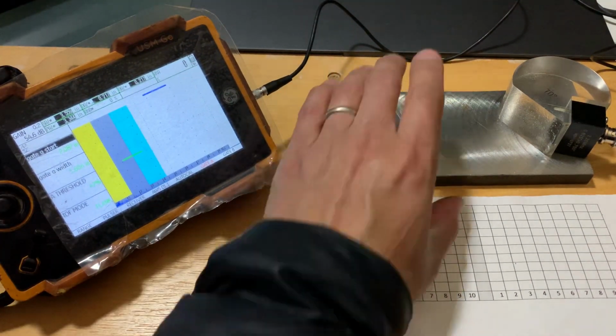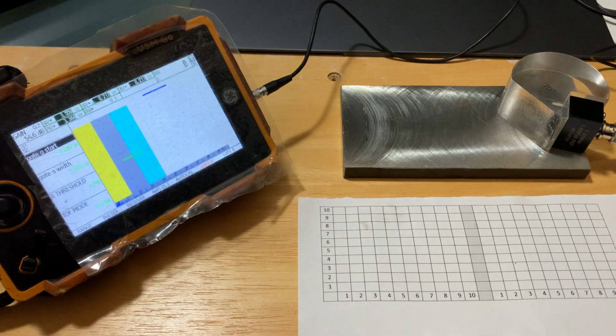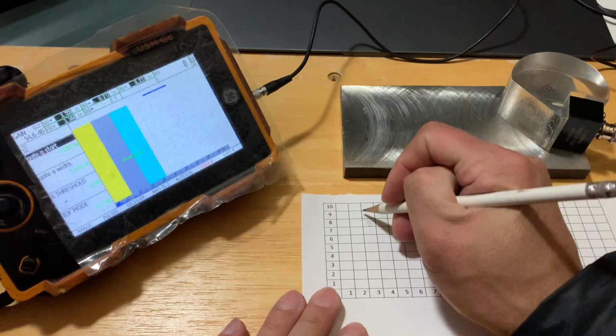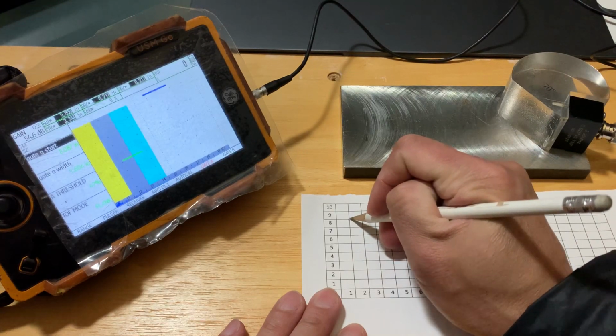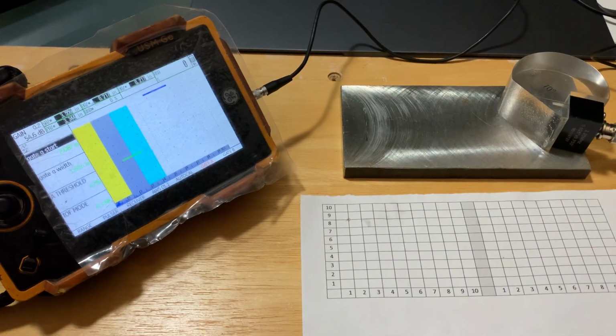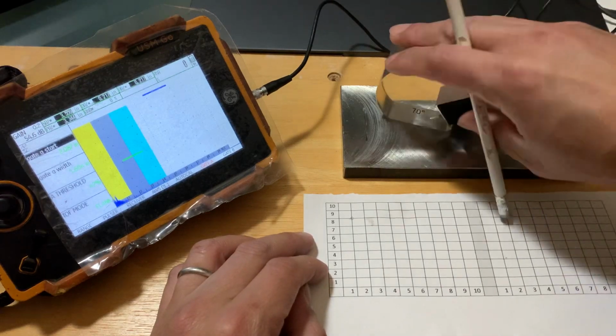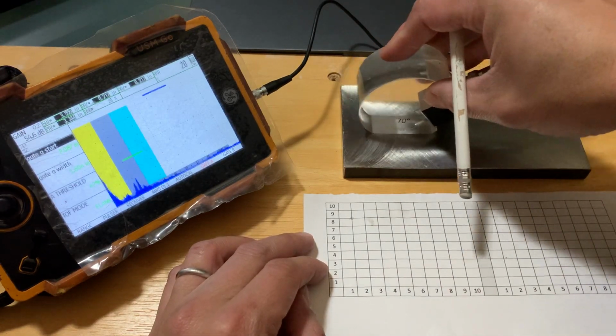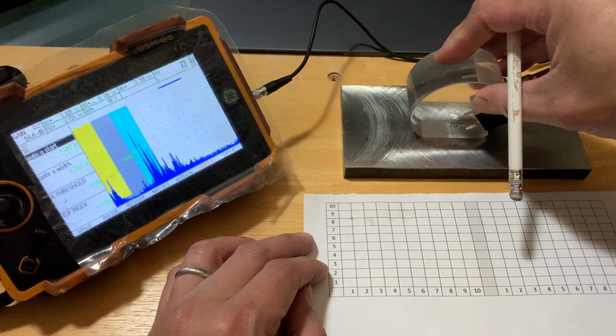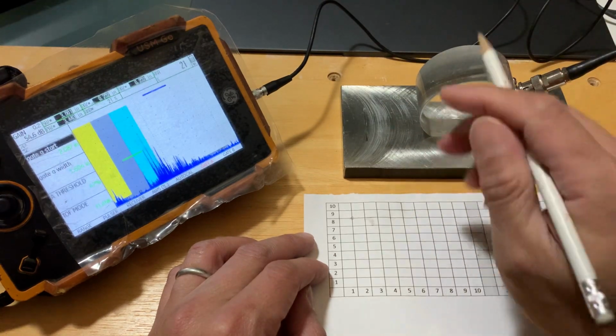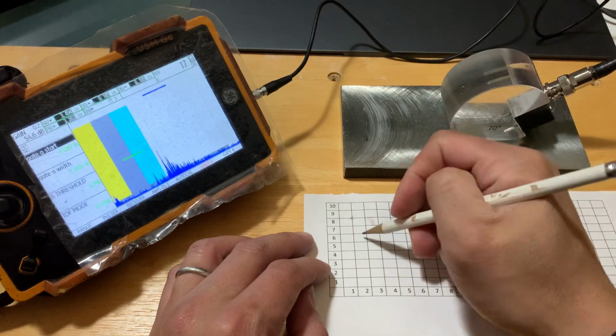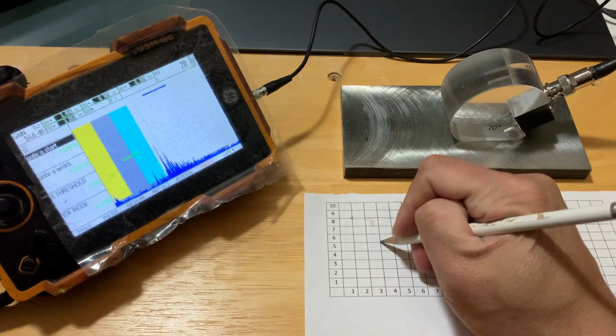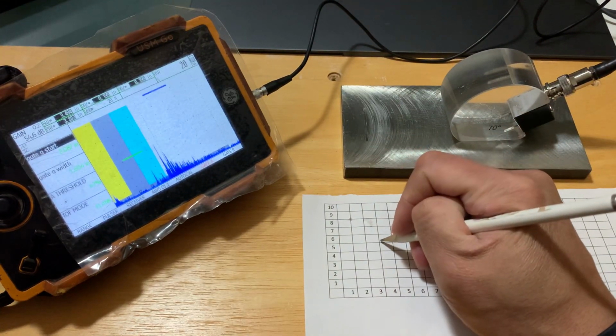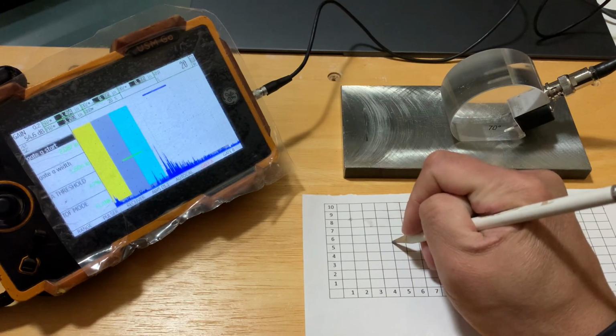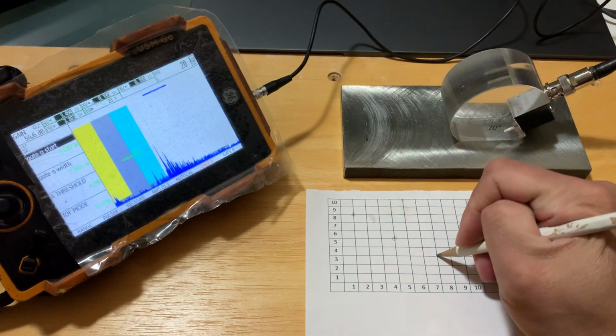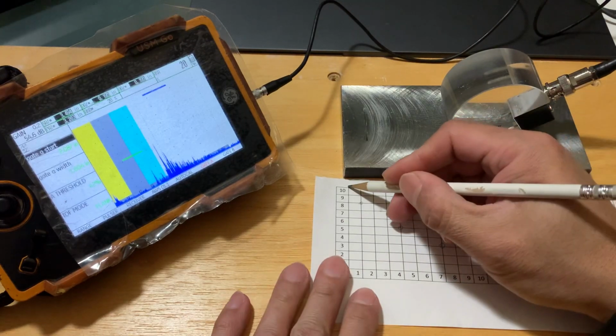And so to shoot a DAC curve or have it considered a curve, you'll need 3 points. And so what I'm going to set it to is 80% for the first indication. I'm going to mark that there. And as you know, as we get the indication, set 80, and the further we move back, it's going to bounce down and bounce back up. The further we move back, the further away and down lower the indication is, because you're going to lose some of the signal due to attenuation. So the next one might be over here, and the third one might be over here. So essentially it makes a curve.